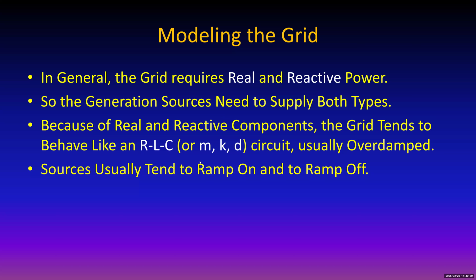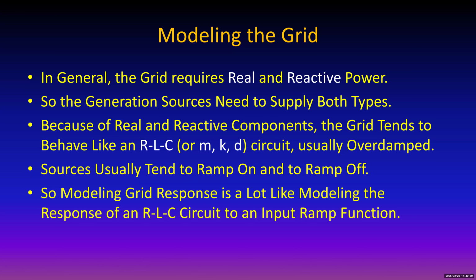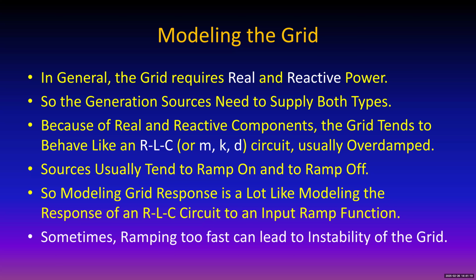Large renewable sources are generally designed not to act as a step function excitation, to turn on and off over a matter of a second or two, though they can do better if there's reason to. Modeling the grid response is like modeling any second order differential equation, with a ramp function or similar, and that's basically what the modeling programs try to do. As we said, if you ramp too fast, it can lead to grid instability, so you need to watch for that.